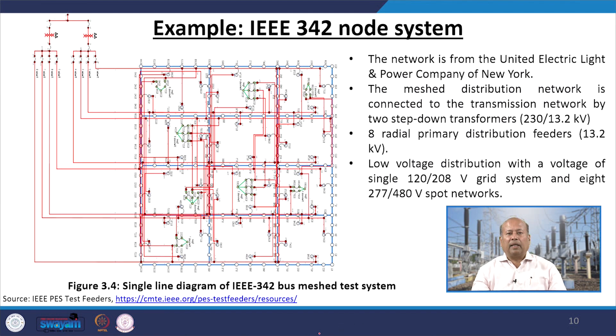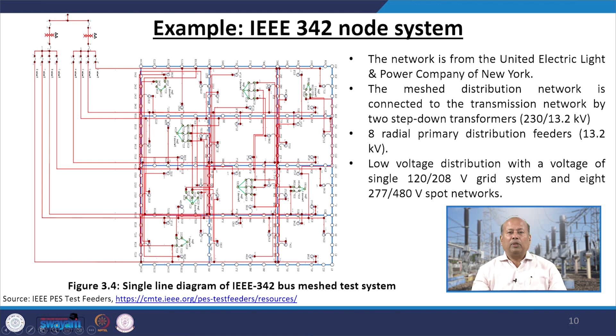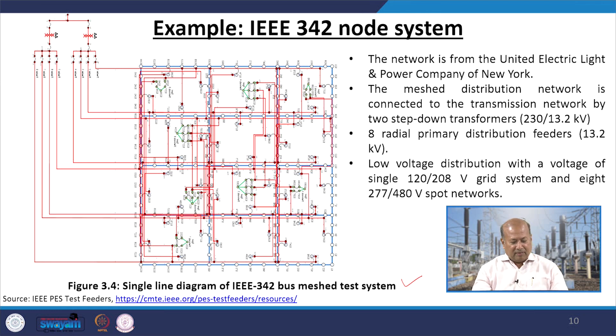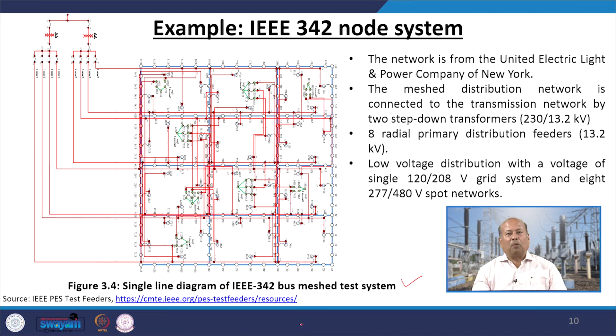We can also look at the IEEE 342-node system, a network from the United Electric Light and Power Company of New York. The mesh distribution network is connected to a transmission network by two step-down transformers (230/13.2 kV), with eight radial primary distribution feeders at 13.2 kV, low-voltage distribution at 120/208 V grid system, and eight 277/480 V spot networks. Looking at the single-line diagram of the IEEE 342-bus meshed system, it is very complicated, and energy can be captured from any corner of the city — good, but too complicated to manage.